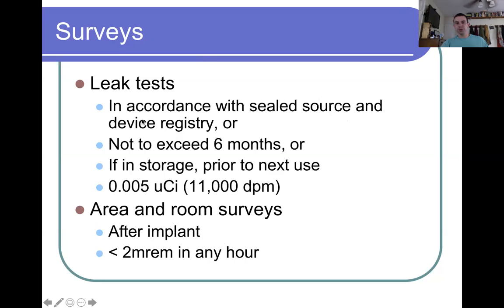Some sealed sources have a device registry, which may say something else. It may say they need to be retested every 3 months, but nothing can exceed that 6 months. So there's nothing that can say, oh, you only need to leak test once a year, because the regulations trump any sort of device registry. So you also have surveys. There's certain situations where it's very important to survey after the source is supposedly withdrawn from the patient. You want to make sure that that source is actually out, especially if you are dealing with something like a 10 curie HDR source. It's very important to know that that source has been withdrawn from the patient and is back in the shielded container.